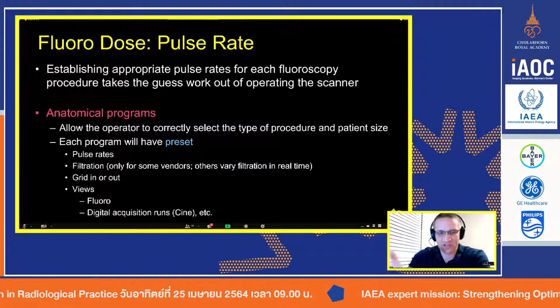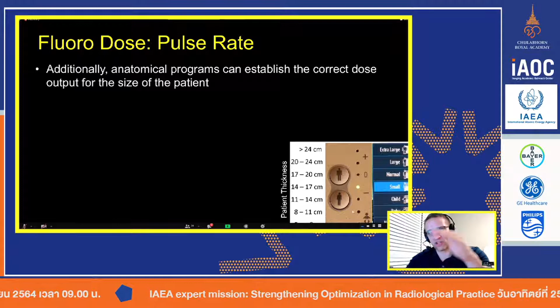So how many fluoro units should you have? Digital images, cine runs, DSAs? You need to work all that out. I talked a little bit about how you need to have the doses set as a function of size. This is just an example of how we do it at my center. I'm not saying it's the right way or the wrong way, and you may do it a little bit differently. Every system is going to have some way to adjust the machine so you can change the output of the machine.